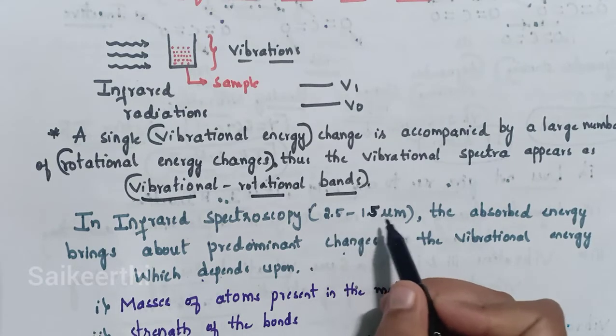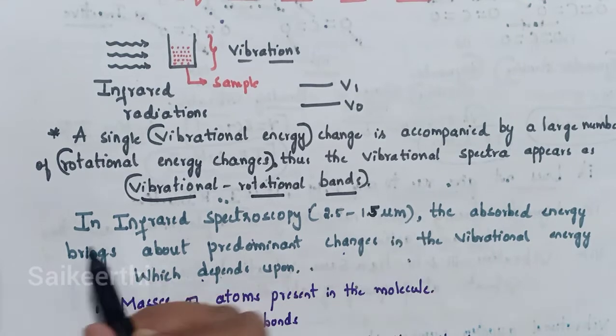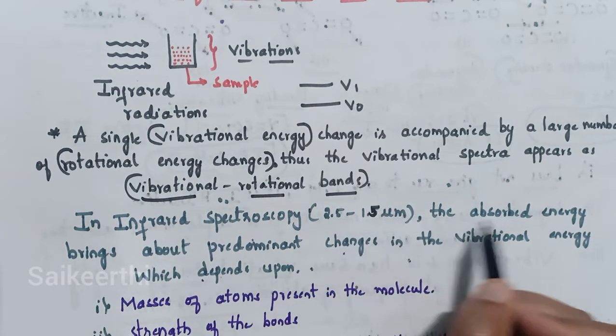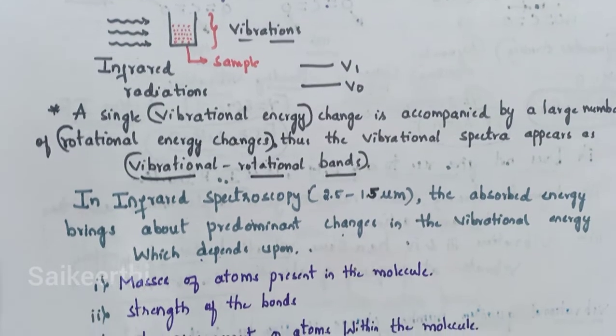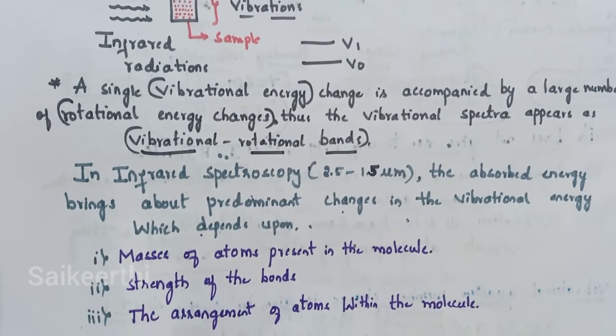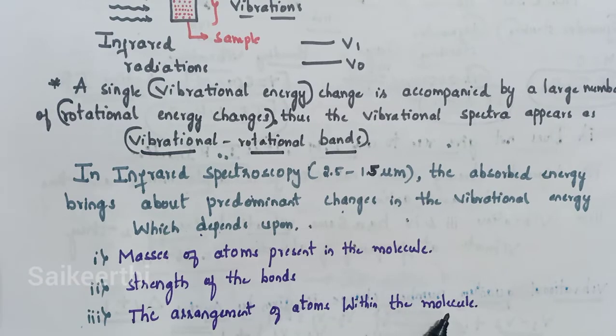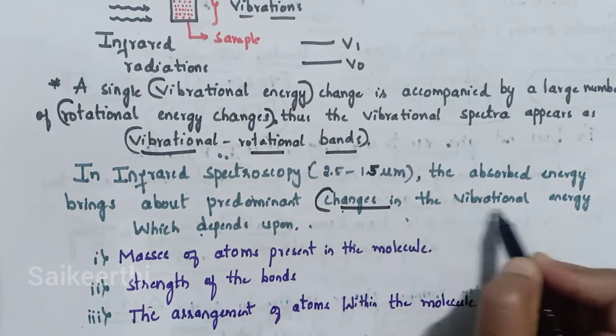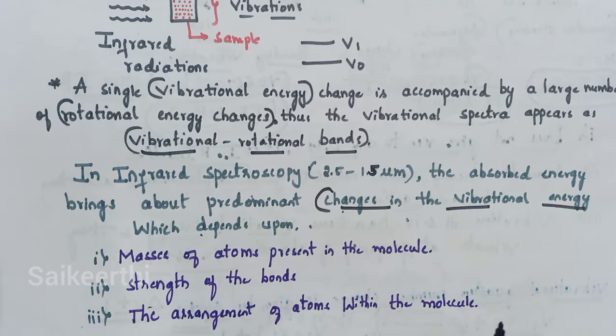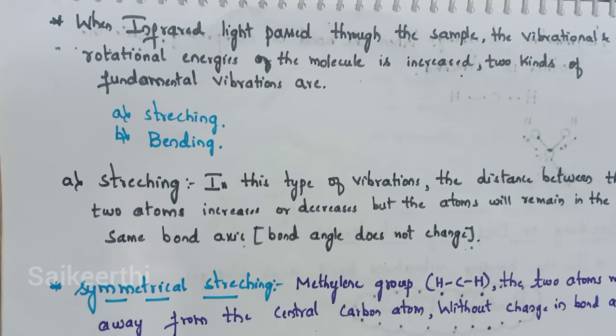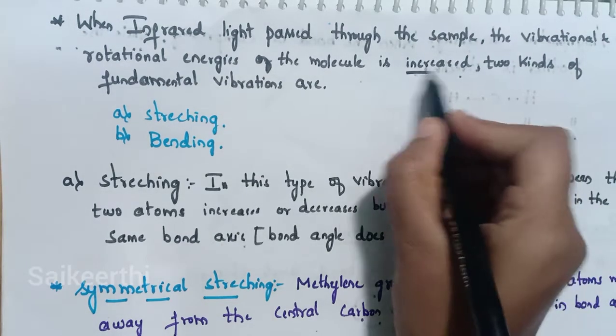Most molecules start to vibrate when they absorb radiation of 2.5 to 15 micrometers, that is in the infrared region. The absorbed energy brings about predominant changes in vibrational energy, which depends upon the masses of atoms present in the molecule, strength of the bond, and arrangement of atoms within the molecule. When infrared light is passed through the sample, the vibrational and rotational energy of the molecule is increased.